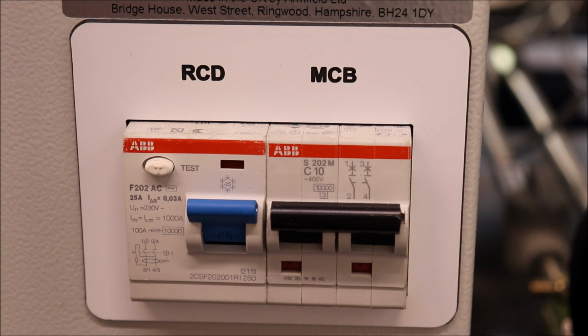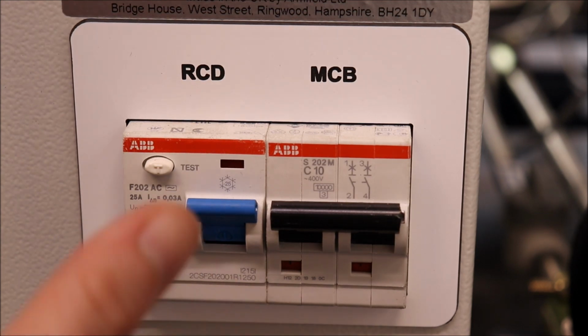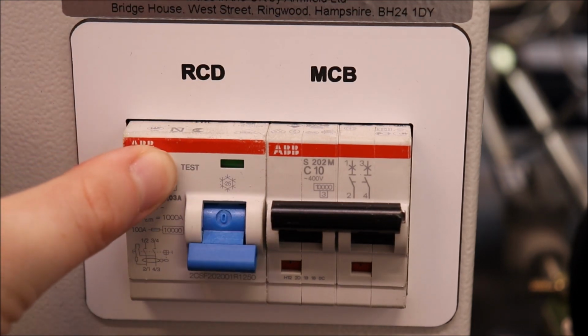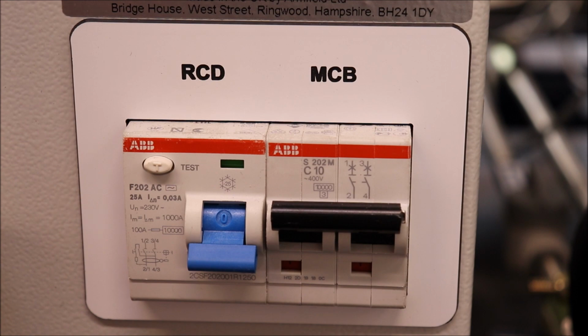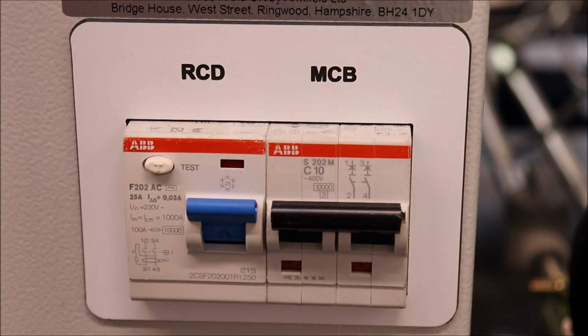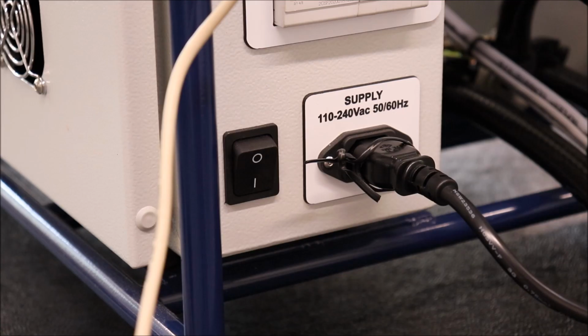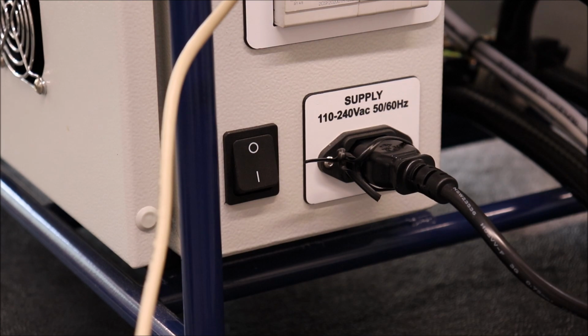Next, check the breaker on the VCC. Press the test button by the blue switch. If the breaker flips, the VCC is good. If it does not flip, do not proceed with the procedure. If the VCC is good to continue, return the breaker to the up position and power on the VCC by pressing the button below the breakers.